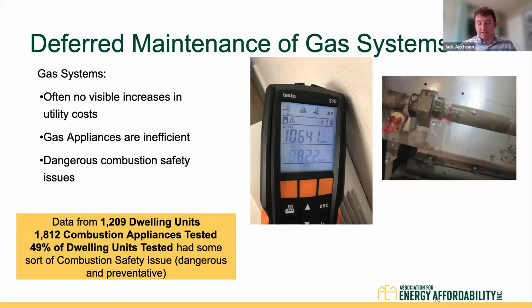Ultimately, what you can take from this is that with deferred maintenance on our electrical appliances, we're probably going to see an increase in utility costs, and the building owner is going to notice that. But on the gas side, unless you actually test for it, you're not going to see these dangerous issues. So you may have the perception that you don't have to maintain the equipment as much because it's not increasing your utility costs. But in reality, you could potentially have dangerous issues at the appliance itself.